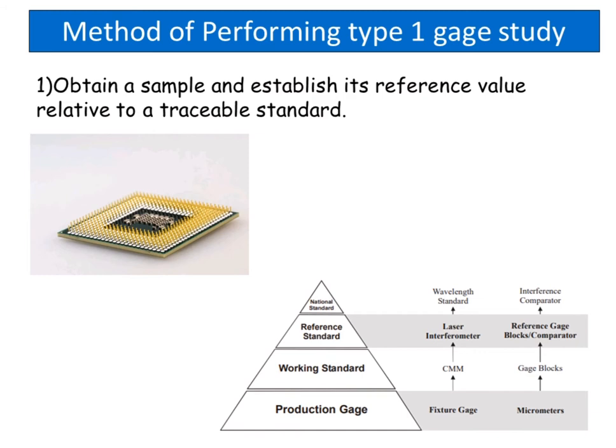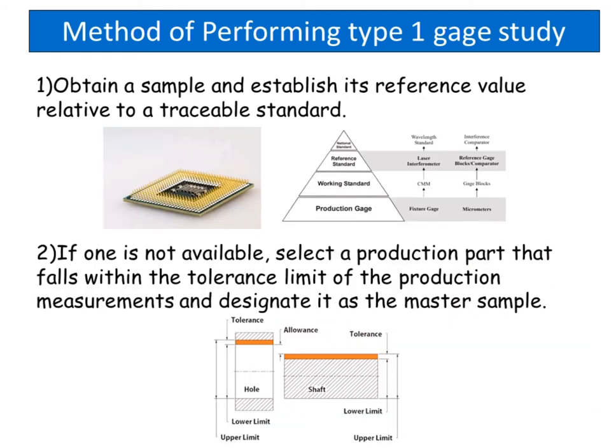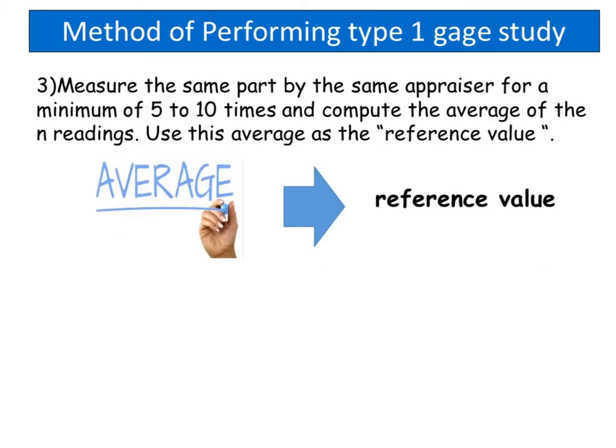Method of performing a type 1 gauge study: Obtain a sample and establish its reference value relative to a traceable standard. If one is not available, select a production part that falls within the tolerance limit of the production measurements and designate it as the master sample. Measure the same part by the same appraiser a minimum of 5 to 10 times and compute the average of the n readings. Use this average as the reference value.